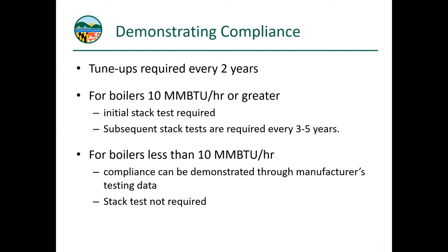There are a lot of companies that come in and perform the maintenance for the units. And for boilers 10 million BTUs or greater, there will be an initial stack test and subsequent stack tests required to demonstrate compliance with the particulate matter standard.